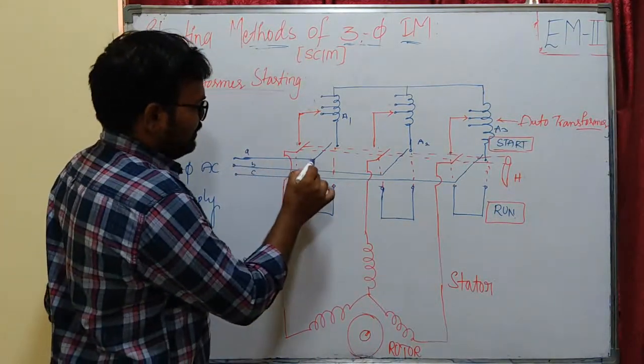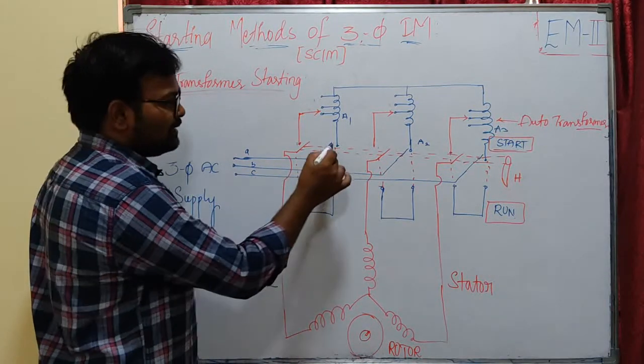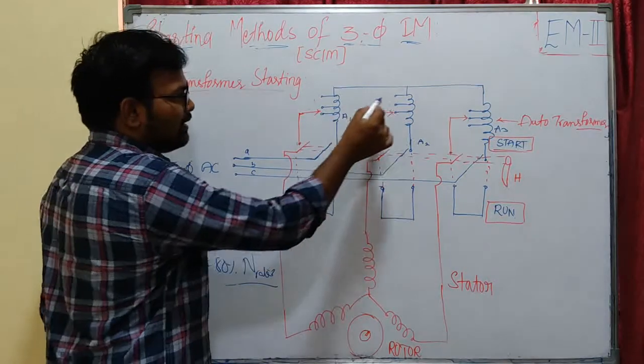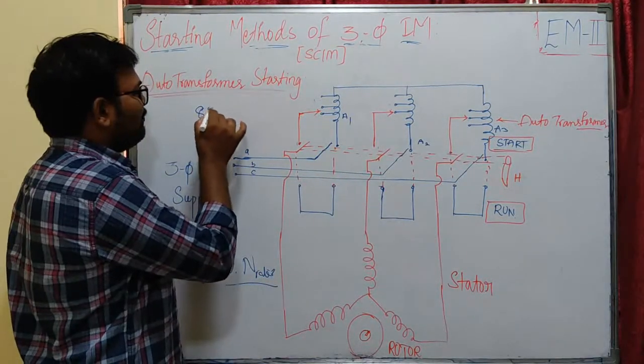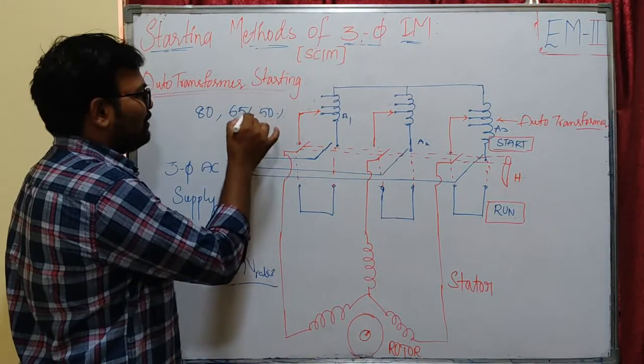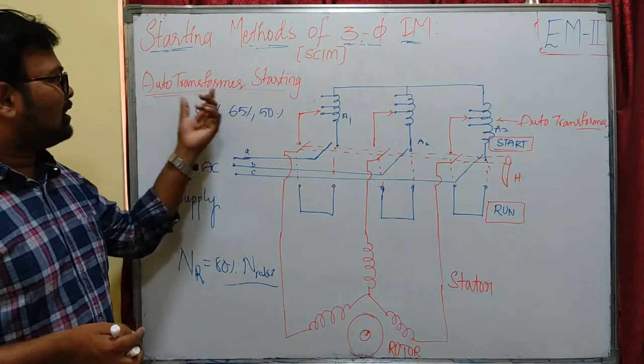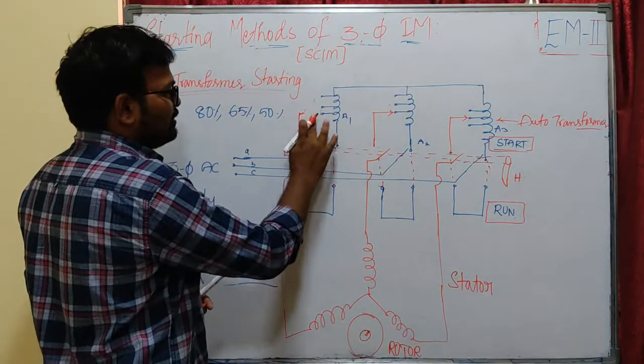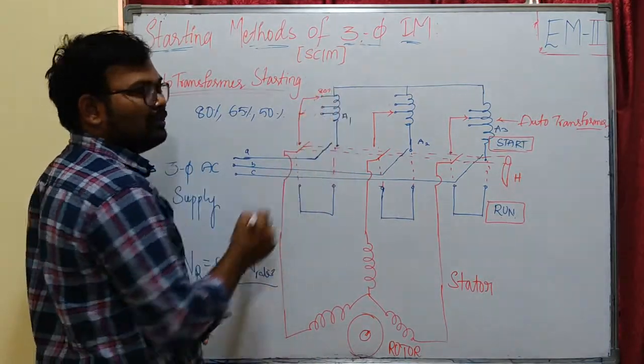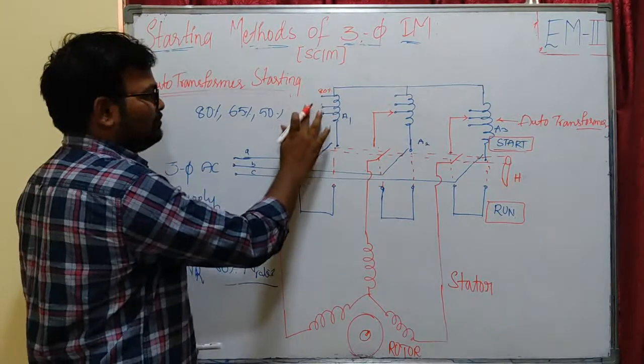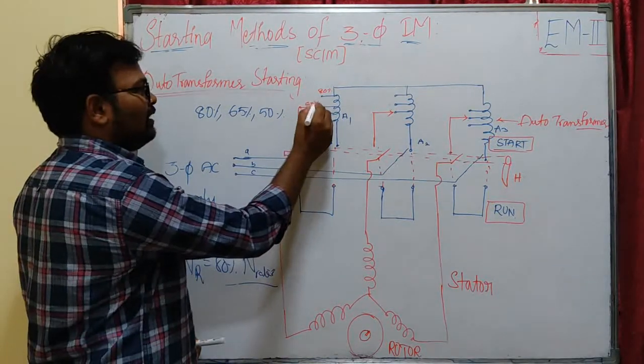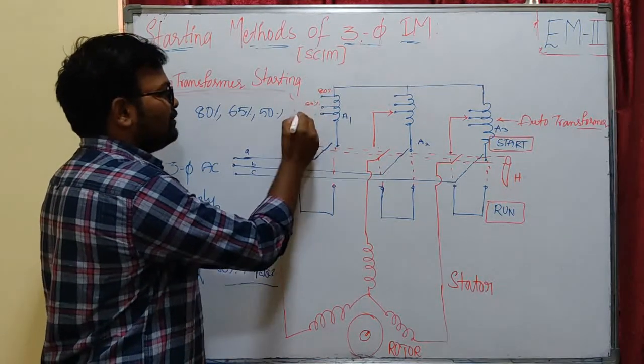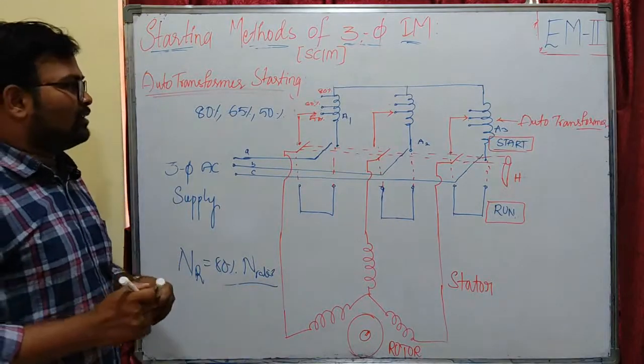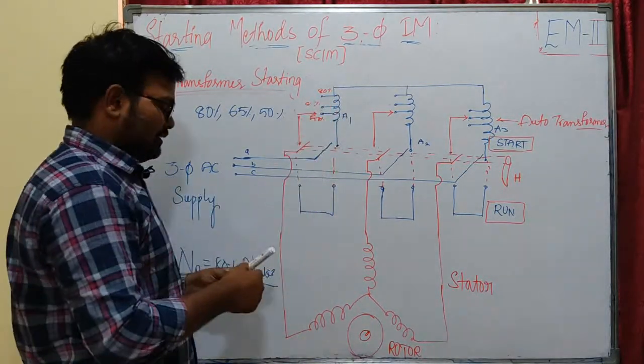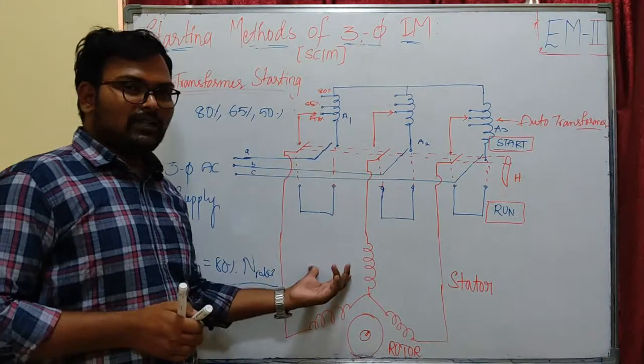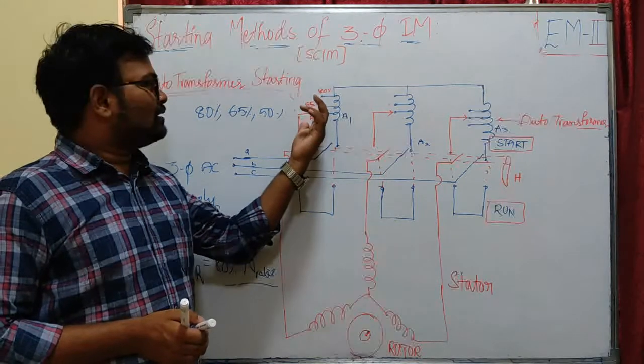You can see here my supply phase, and this will be connected to my auto transformer, and these three are tappings on the auto transformers with voltage ratios of 80%, 65%, 50%. These are the common tappings on our auto transformers for auto transformer starting. If you connect this switch to this tapping, you will get 80% of our supply voltage at the stator. If you connect it here, you will get 65% of your rated supply voltage. If you connect this switch to this position, you will get 50% of your supply voltage. So we can get whatever voltage is required. Depending on the local condition, we can get voltage ratios like 50%, 65% and 80%.